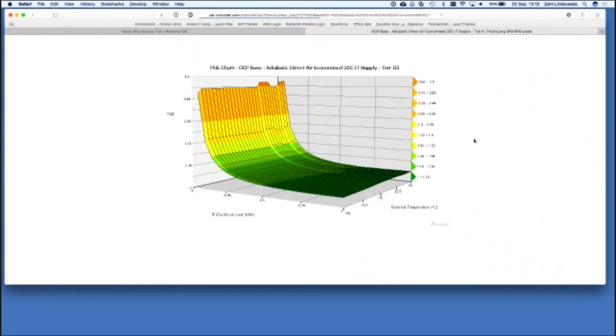Let me see if I can zoom that a bit. What the PUE surface does is, essentially we've got PUE on the vertical axis here, and we've got utilization on this axis down here. So this is essentially the data center being fully loaded, 50% loaded, and then we've got external outside air temperature here. And you can see the PUE under essentially any of those points.